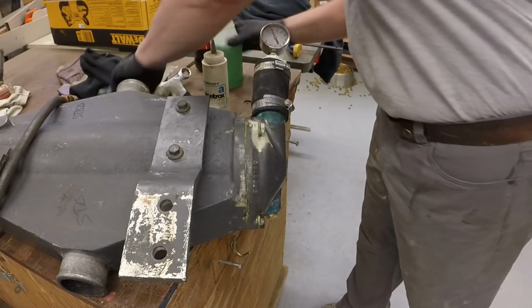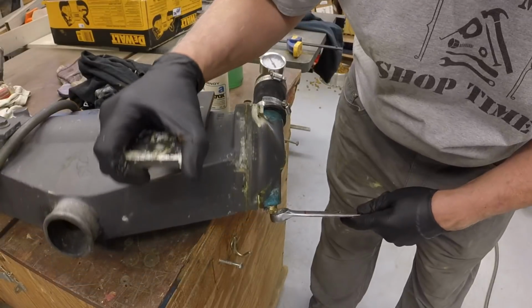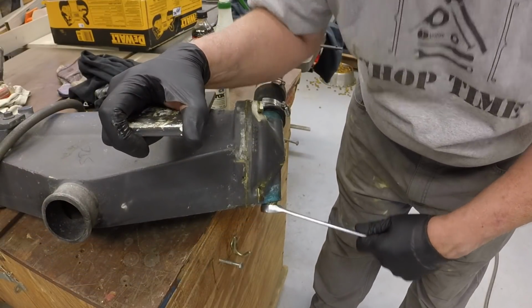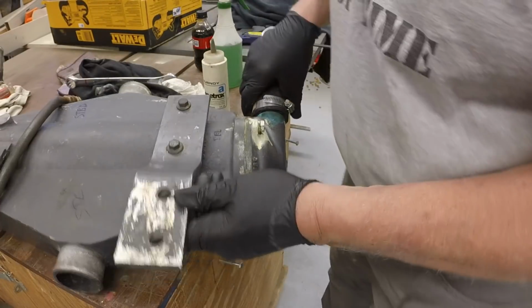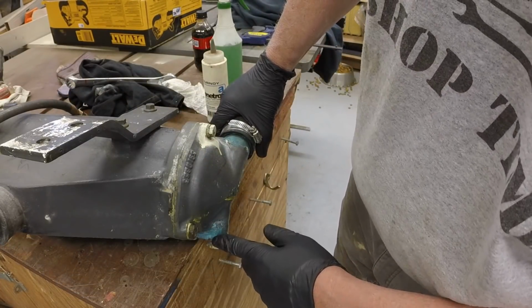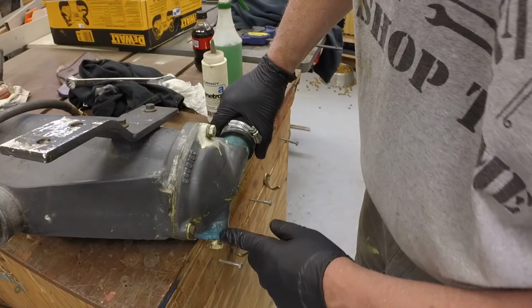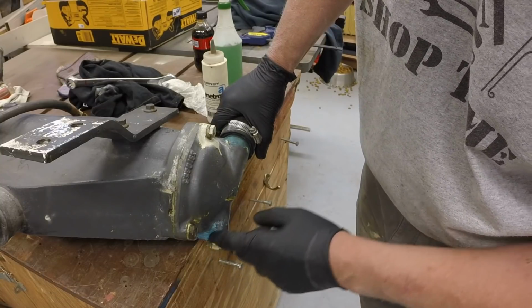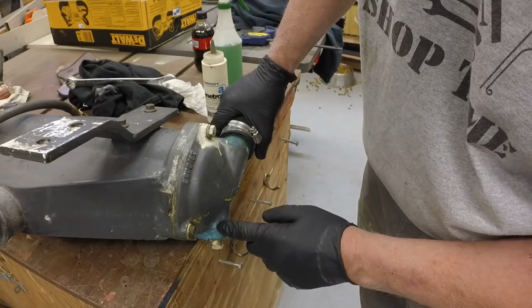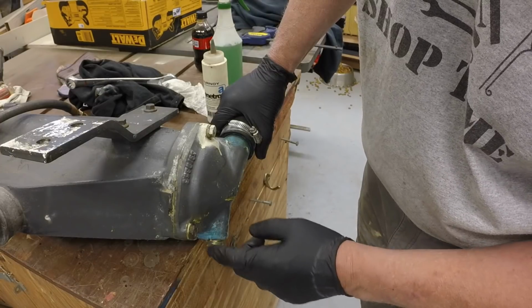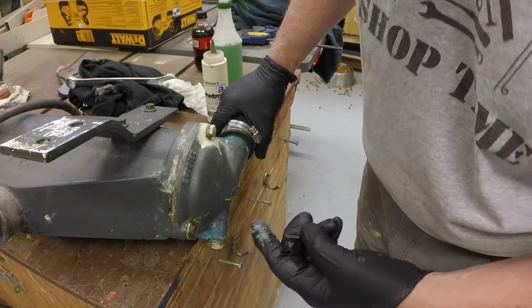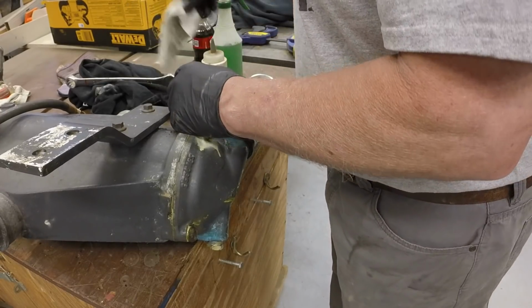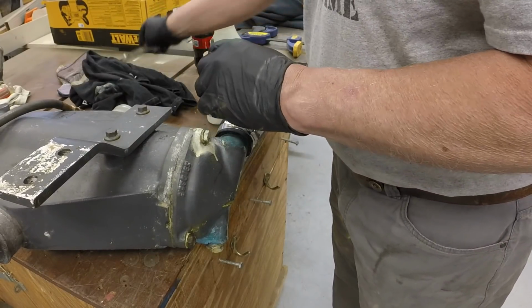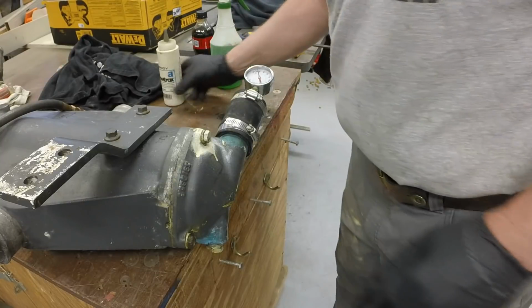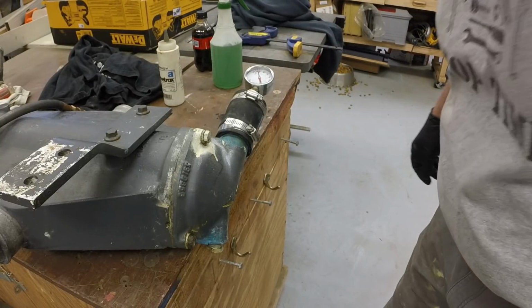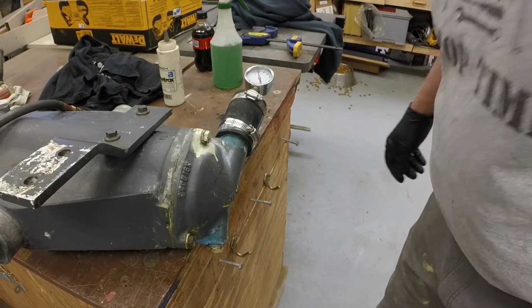Alright, it looks like that stopped the leak. Be careful, I don't want to put it in too tight, because it's tapered thread, so there's a risk you could split this housing if you're not careful. So that looks good at this point. All right, I think it's holding pressure.